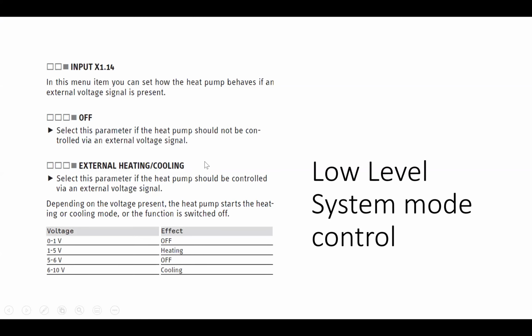Third party zone module system, X1.14. We could have it give us a 0 to 10 volt signal into X1.14, and it will give us mode selection. Because you must remember, the way that the unit selects its mode between heating and cooling, if it isn't forced into a mode, is via the outdoor sensor, the set points we put on the outdoor sensor.